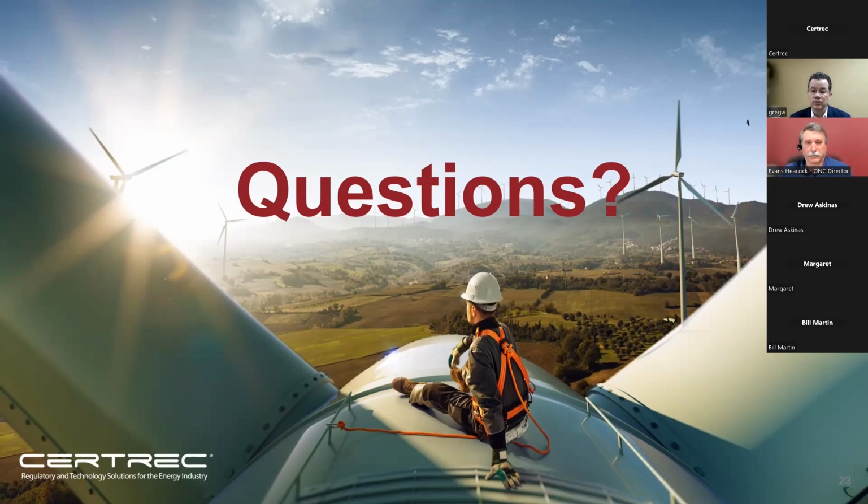All right. This question is from Andy. I believe, Greg, you already touched on this, but what is the sampling rate in hertz or per cycle of the smart block device? Right. It's upwards of 128 samples per cycle. I won't spend a lot of time on this now because we already talked about it, but for rotating equipment and certain asset health monitoring applications, we vary that down quite a bit and extend the duration quite a bit as well to get higher resolution. And so it's a whole range.